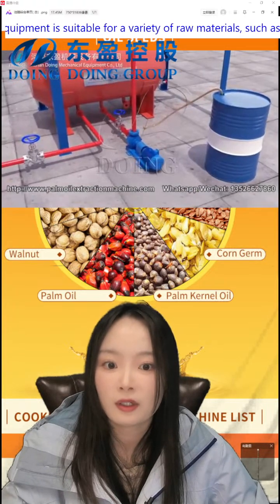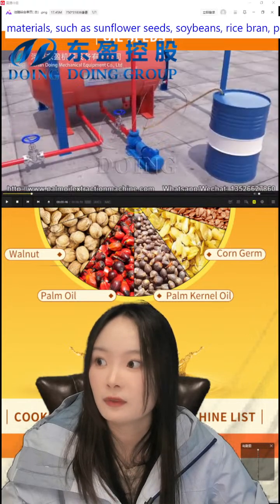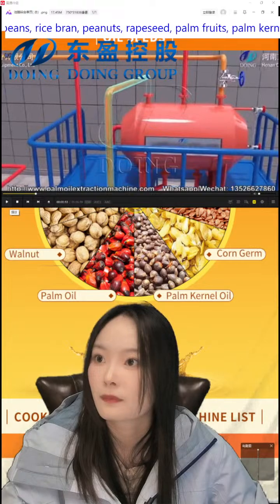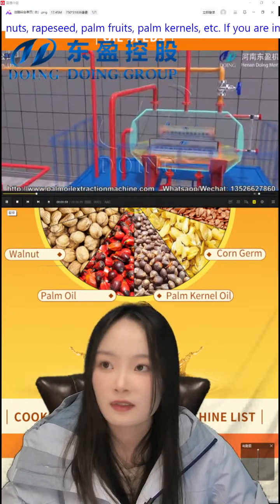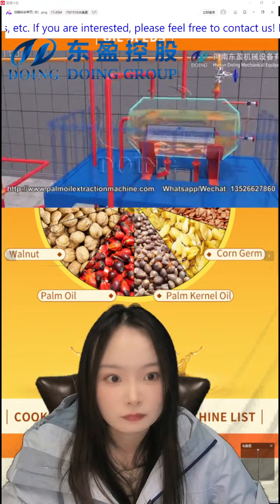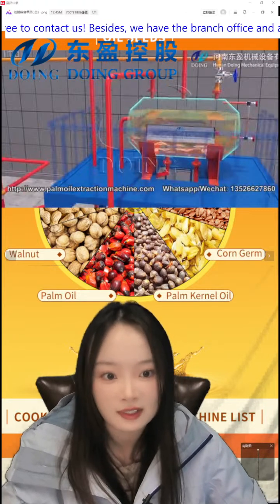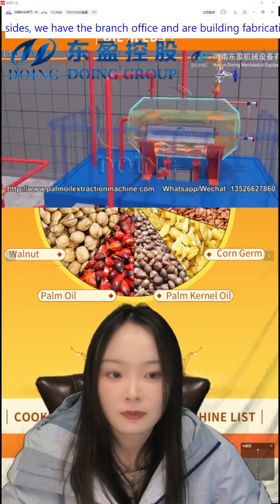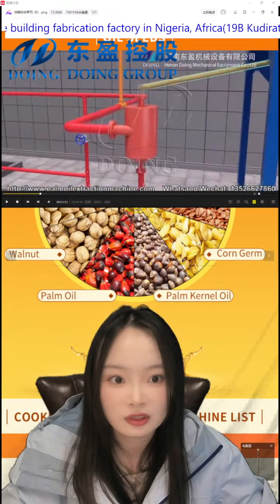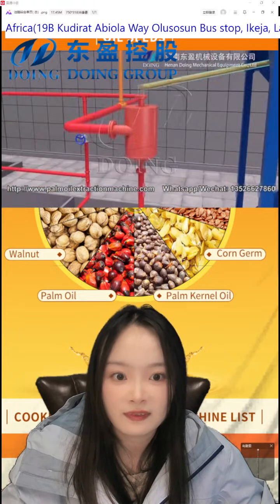This part is the thermal oil recycling system. There are a high-level tank and a low-level tank. This is the high-level tank. The high-level tank is used to remove the air and water in the thermal oil, to avoid the thermal oil containing too much water and air, which affects the heating effect. And connected to a higher level is this one. This is the gas liquid separator. It is used to remove water and air.